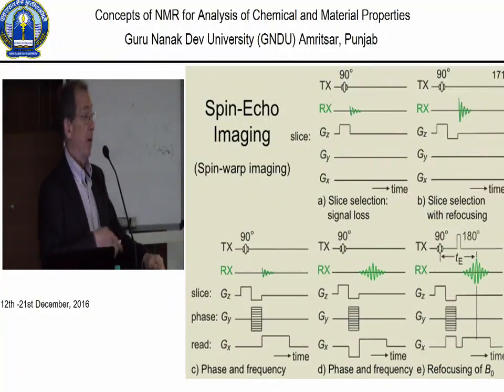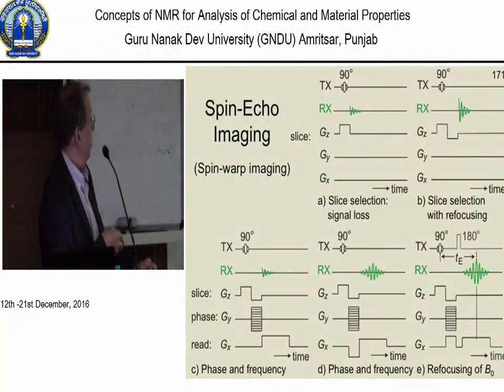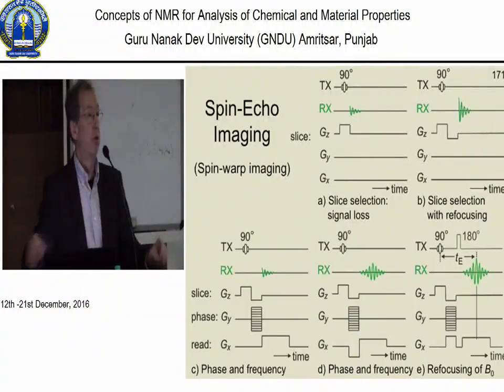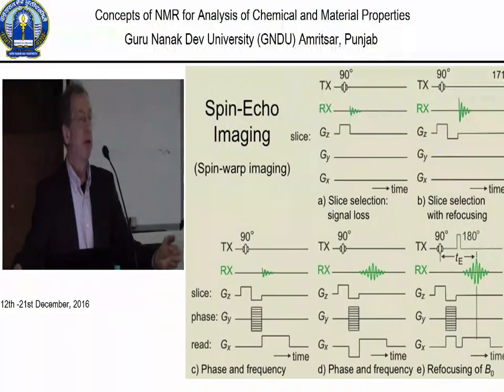One can get rid of that by taking a Hahn echo on top of the gradient echo. Now you put in another 180-degree pulse here. You make the gradient echo coincide with a Hahn echo. That means also that that negative pulse here now becomes positive. And then you can record the echo train, and it now looks higher than this one because the effect of magnetic field inhomogeneity is reduced. And this for a long time was a standard method in imaging because people argued, rightly so, it gives you the best resolution.